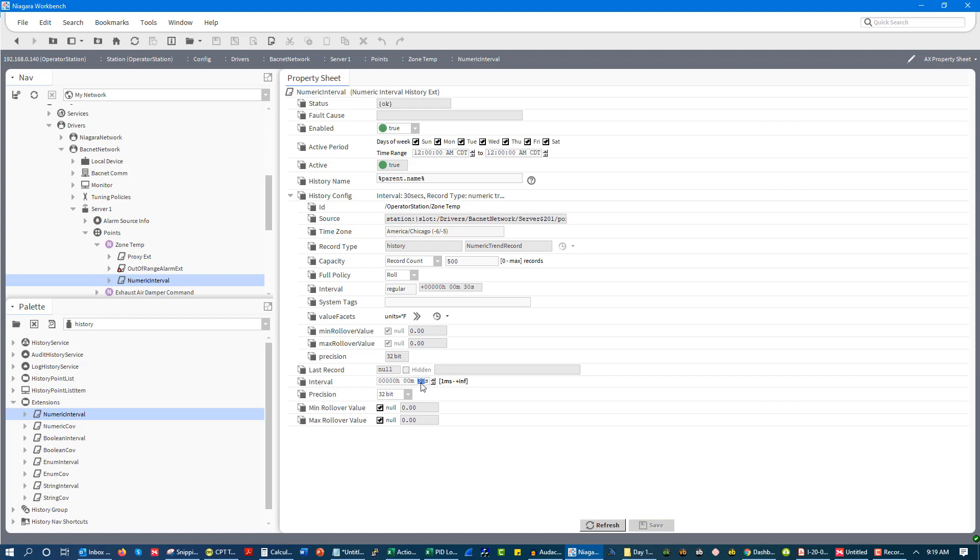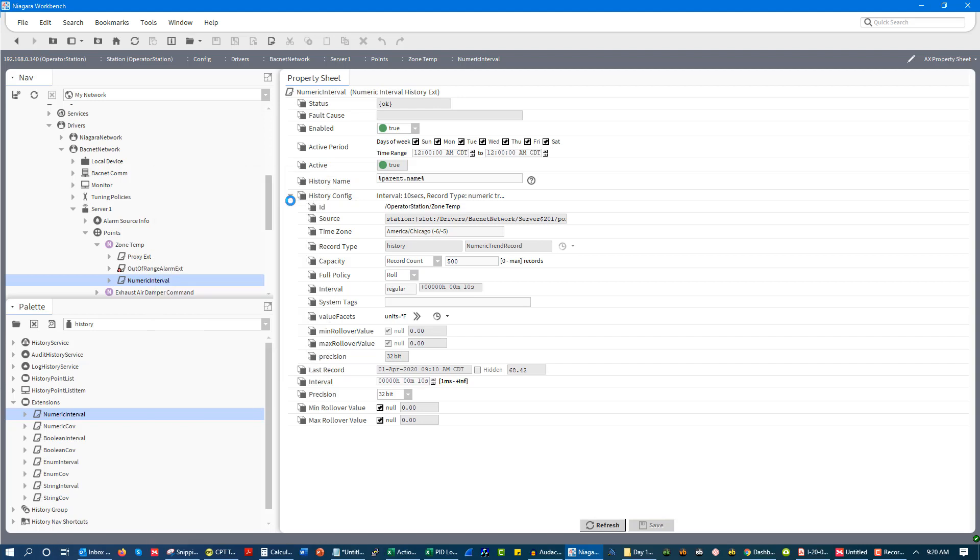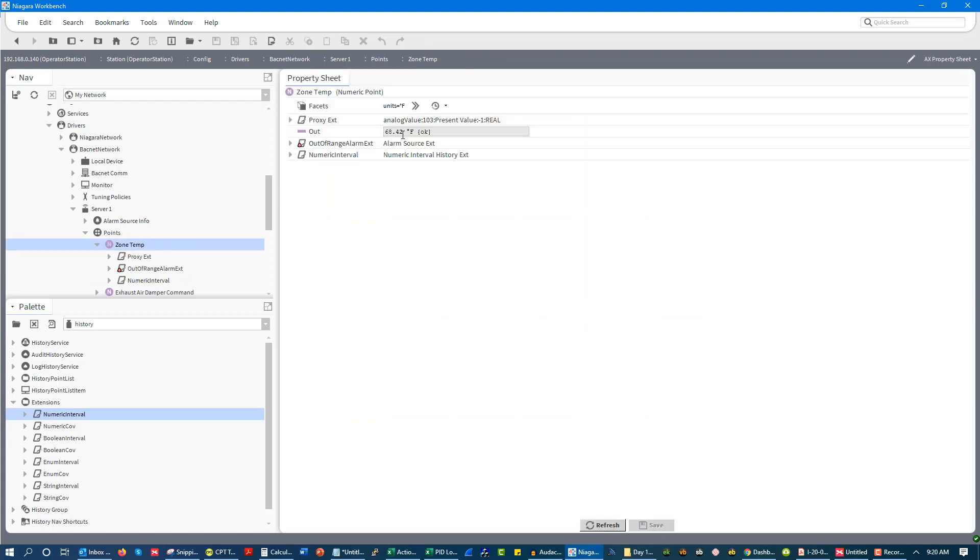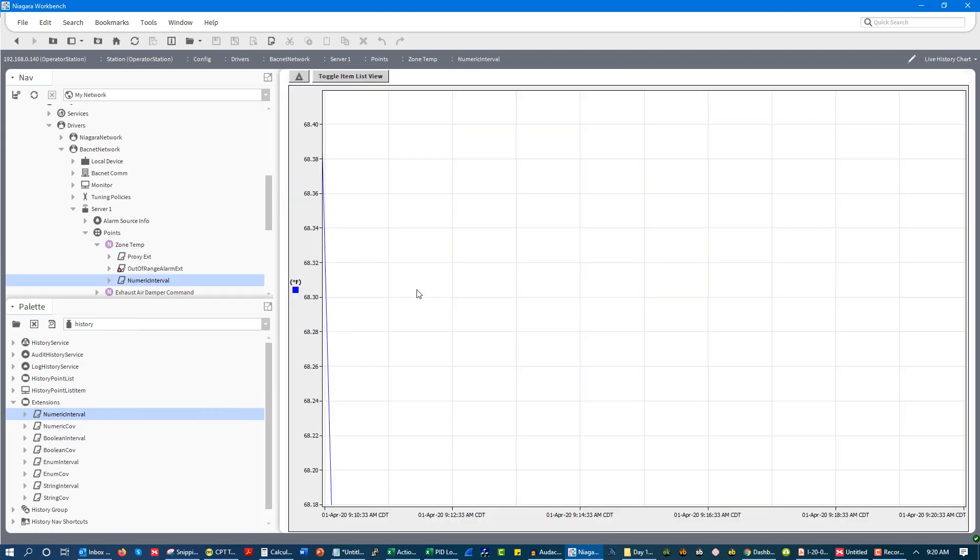I'm going to do something. Yeah, I'll do like 10 seconds. That way, while I talk, it's going to start trending. And so it's going to start taking time samples from this. So we've got our temperature point. And our temperature point now has two extensions. One is an alarm, and one is a history or trend extension. Now what that's going to allow me to do is I'm going to have this kind of history chart. And you can see my zone temp staying pretty steady across the board. I like to keep my office pretty cool. So you can see it's 68 degrees, sitting pretty steady at 68.42 degrees, because I like to keep the place that I work pretty cold. And we can see that the actual trend log right here, the live history chart, we can see kind of how it's fluctuating right here.